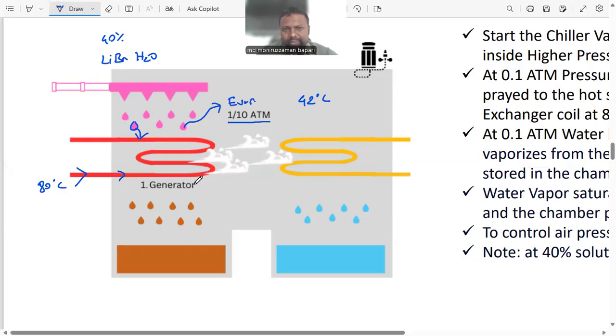Remember, to make evaporation happen, we need latent heat. In this particular scenario, the source of latent heat is the hot surface, or hot water running through this coil. As this hot water inside the coil provides the latent heat, it cools down, and from a higher enthalpy level it goes into a lower enthalpy level. Let's say around 60 degrees centigrade is the water out temperature. So after this generation, we have concentrated lithium bromide stored at the very bottom, and water evaporates and stays in here.